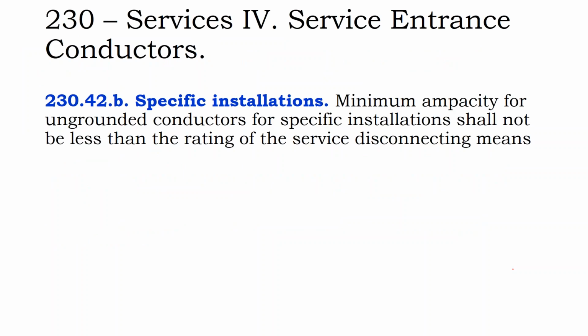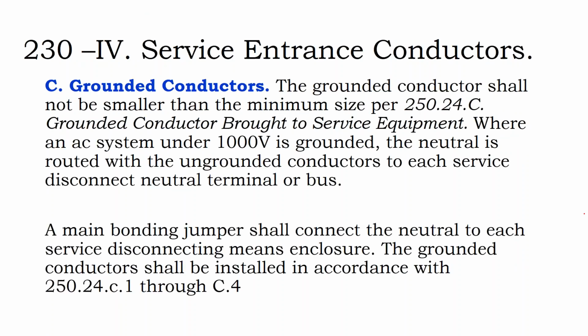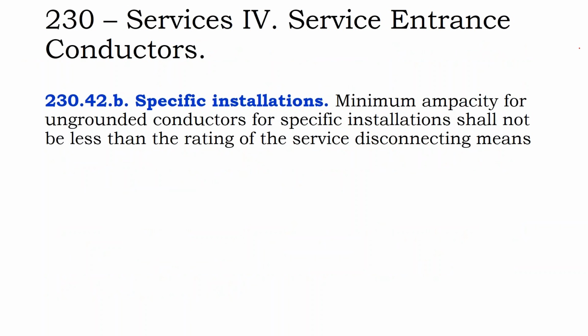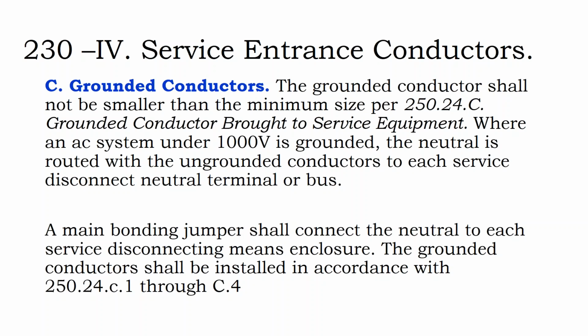Let's see, then we get into minimum ampacity, where it just says, even if you're doing a service that has a 2-volt, you're just trying to power a USB thumb drive. Very low voltage appliances, there are minimum ampacities for your conductors to consider as well. For grounded systems under 1,000 volts. So we'll see some of these minimum requirements show up on our charts a little bit later in the program.